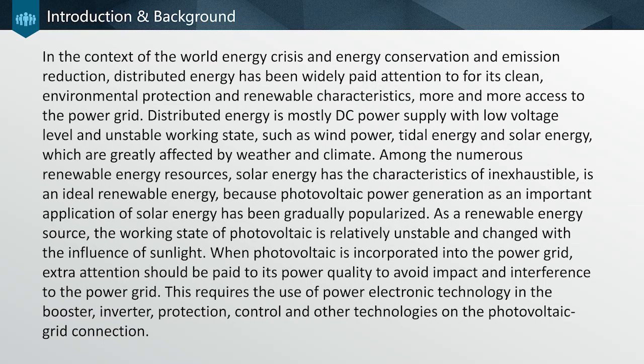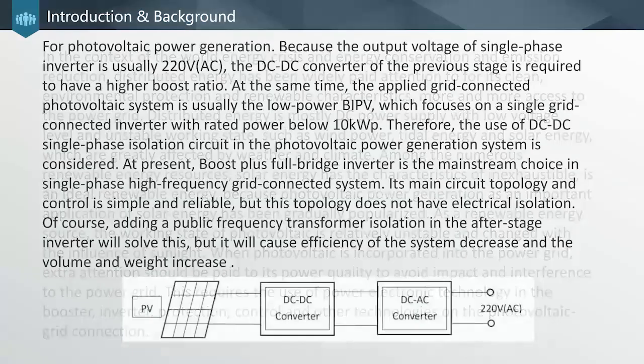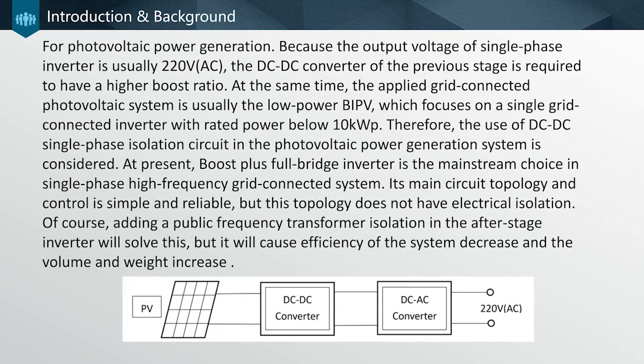When PV is incorporated into the power grid, extra attention should be paid to power quality to avoid impact and interference to the grid. This requires the use of power electronics technology in the booster, inverter, and control for PV grid connection. Because the output voltage of a single-phase inverter is usually 220V AC, the DC-DC converter as the previous stage requires a higher boost ratio. The applied grid-connected PV system is usually a low-power BIPV system focusing on single grid connection with rated power below 10kW, so the use of a DC-DC single-phase isolation circuit in PV power generation systems is considered. At present, the boost plus full-bridge inverter is the mainstream choice in single-phase high-frequency grid-connected systems, with simple and reliable main circuit topology and control.